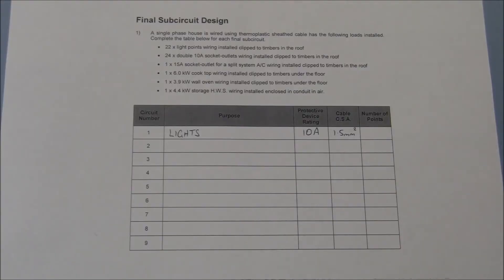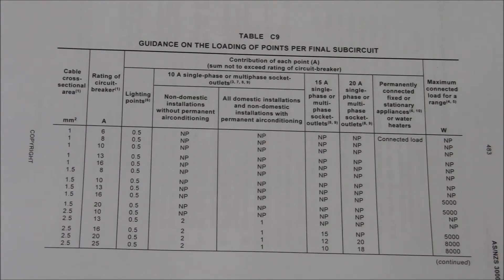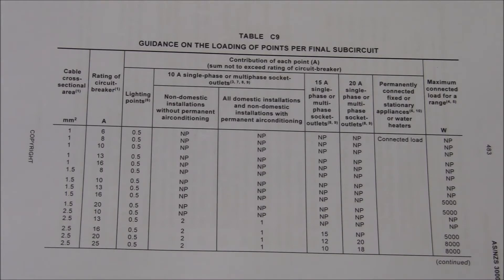Next, I'll refer to table C9 to see how many points I can put on a circuit. Table C9 provides guidance on the loading of final sub-circuits. For a 1.5mm squared cable with a 10 amp circuit breaker, each lighting point contributes 0.5 of an amp towards a total. Therefore, I can put a total of 20 lighting points on each circuit. As my installation has 22 lights, it'll exceed that. It's my preference to have two lighting circuits, so I'm going to allocate circuits 1 and 2 to lights with 10 amp breakers and 11 lighting points each.